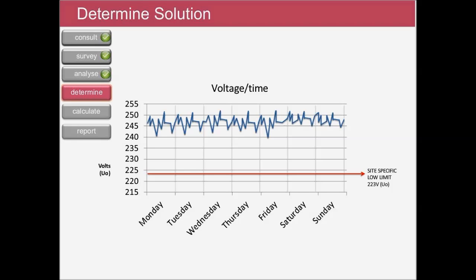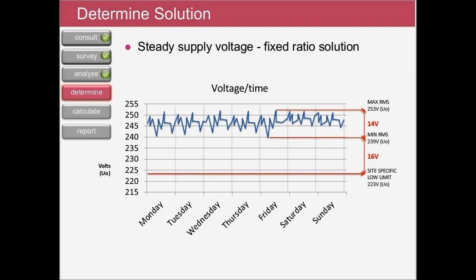So to demonstrate this, we've plotted a simple voltage and time chart. The red line here represents a site-specific low limit ascertained from the study. In this scenario, the voltage supply is fairly steady with only 14 volts between the extreme measured RMS voltage values, the maximum and the minimum if you like. This kind of profile is inherently compatible with fixed ratio voltage management solutions, which are generally cheaper than high-tech or dynamic versions. As you can see, the minimum value measured here in the logging period is some 16 volts above the site-specific low limit, which means there's some scope for reduction. It is of course important to remember and try to ascertain the optimum voltage or range of voltages that are going to complement the majority of load-bearing equipment at each specific site.